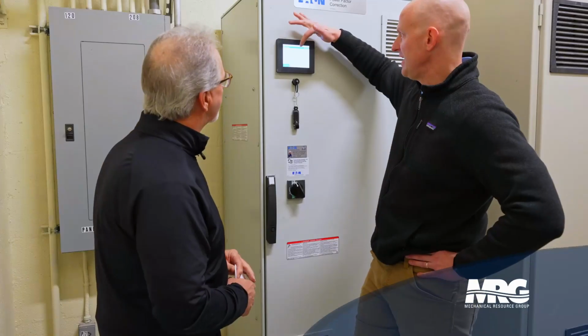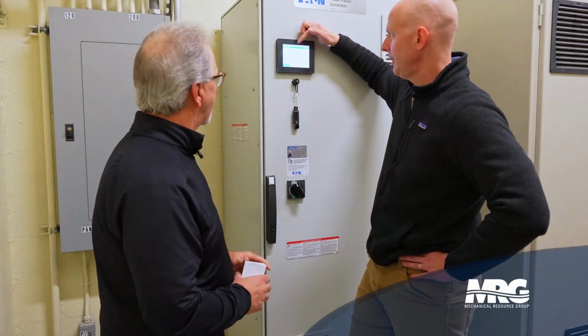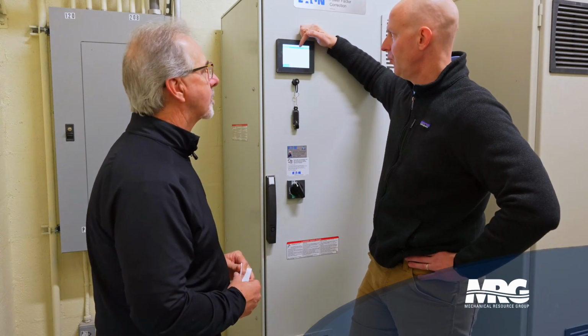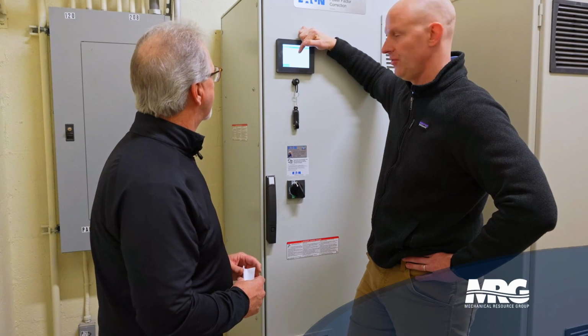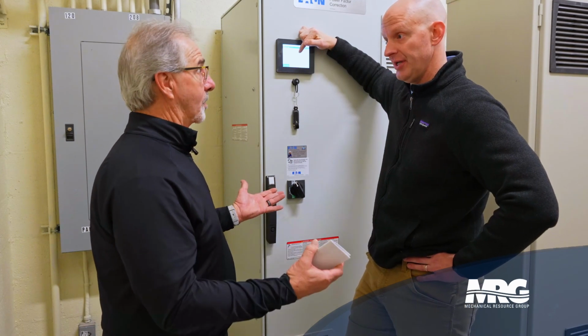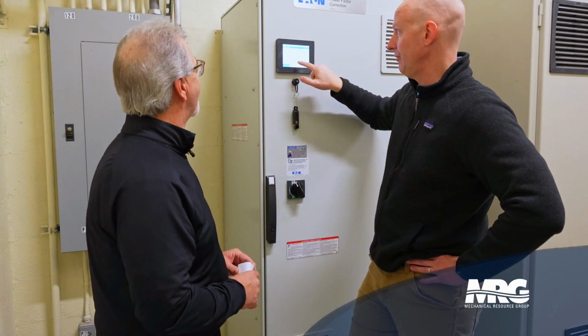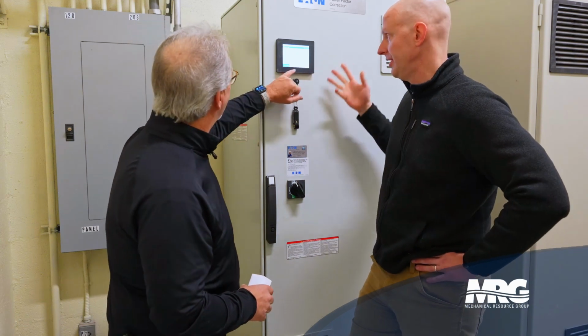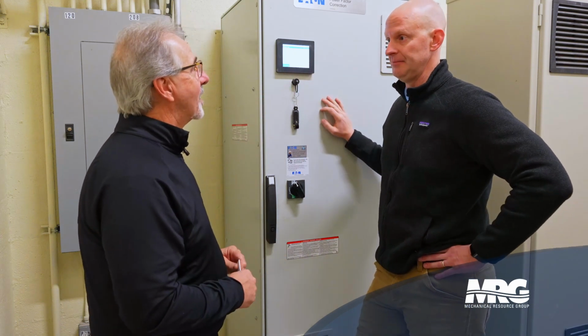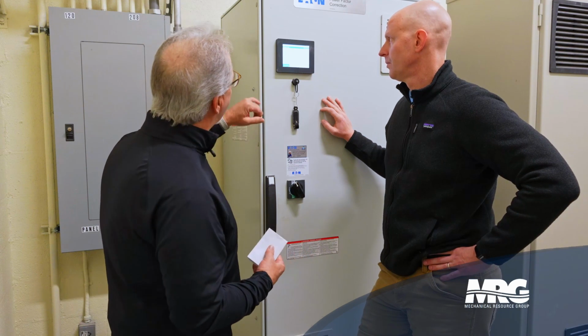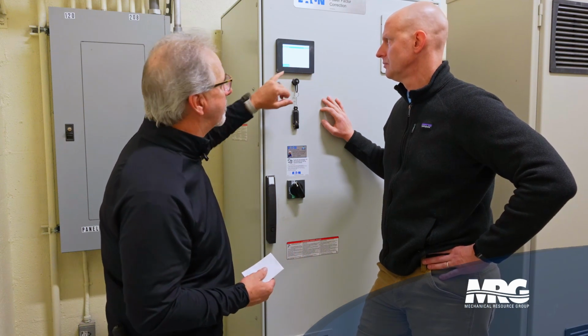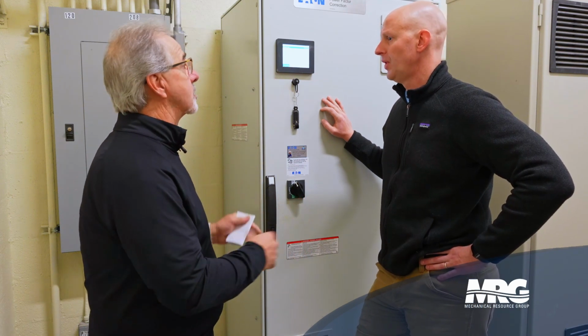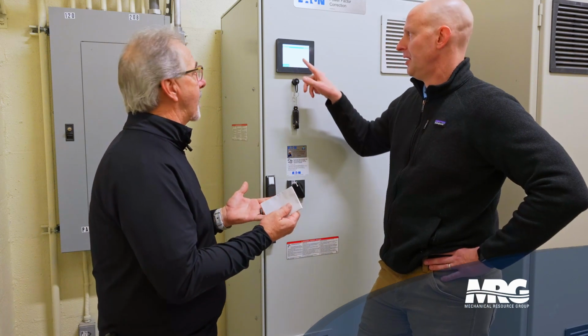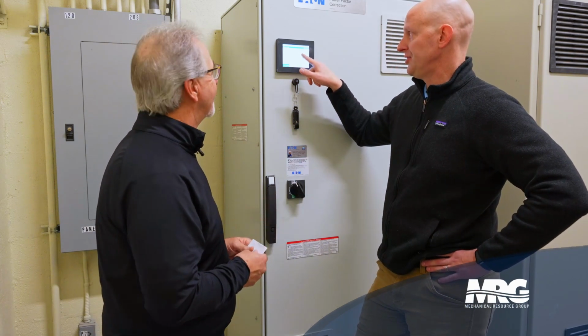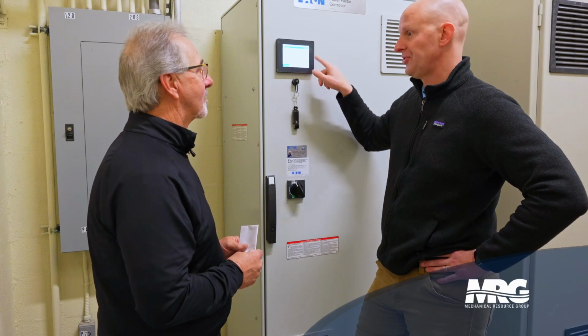Okay. So this is each leg? This leg is 1, 2, 3? Correct. And so we got 201 amps still coming in. Correct. And then about half of that is dirty. It's dirty. And we're cleaning it up, and we're putting out 202 amps, and it's clean. Yeah, it's clean power, but then the other thing that you'll notice is we have a little bit of a phase imbalance, or a current imbalance. Right. And the reason why you have a current imbalance... Because you got 200 on leg 1, 250 on leg 2, 230.